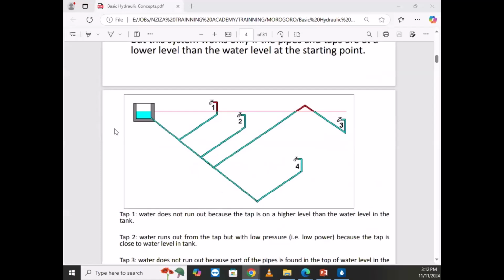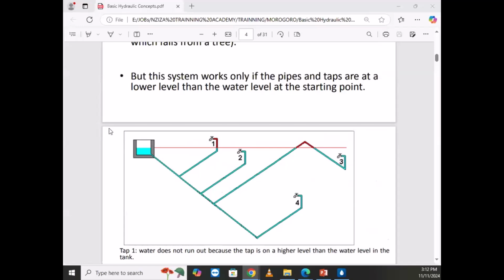But most of the time, we face a challenge when designing, of putting a tank where gravity will not allow you to reach all of the areas. For example, some engineer proposed just a tank, supposing that the system would be governed by gravity. He proposed just a tank here. The water was reaching all parts of the network except the part above the tank.